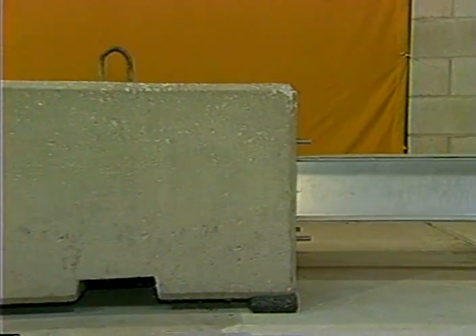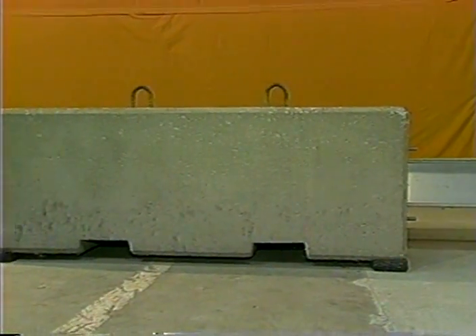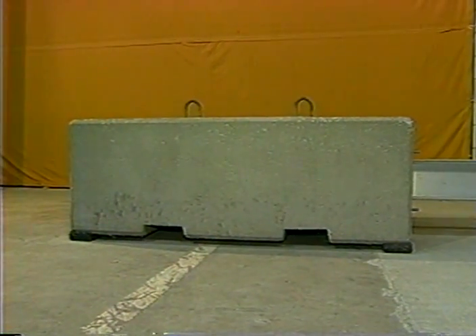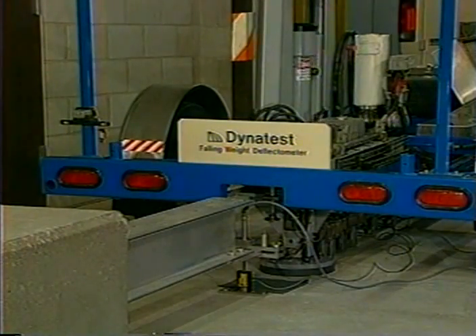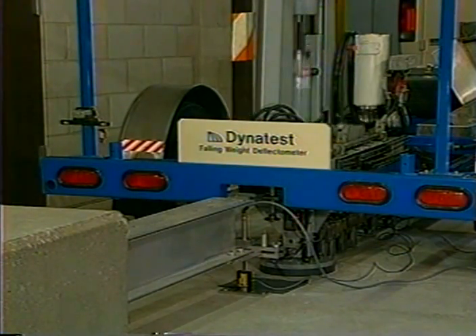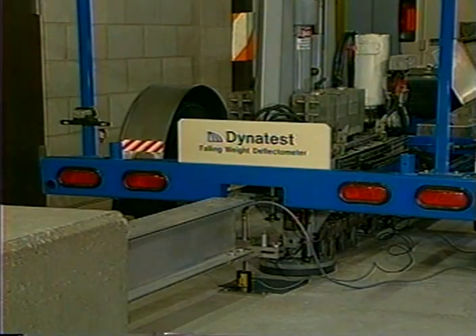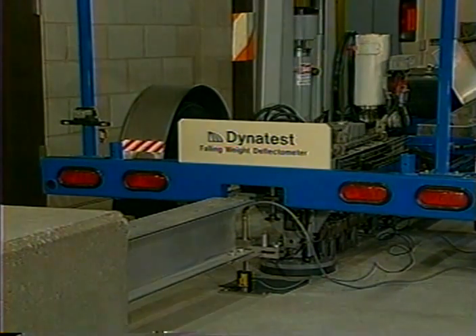The aluminum beam and the big concrete block it's attached to are designed to isolate the LVDT. That way, the LVDT can provide an accurate deflection measurement almost completely independent of the impulse that comes through the floor and up into the beam. But it's impossible to totally isolate the LVDT.